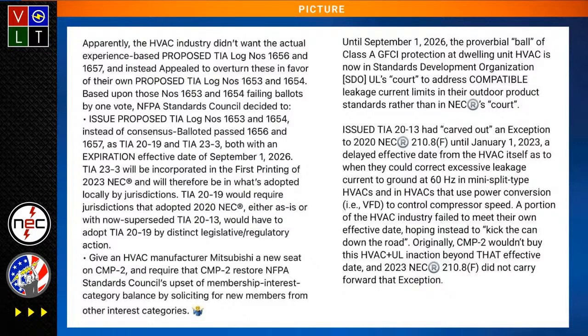There's a lot of these gray areas, and I feel this is kind of the whole point of why we're doing this with Code Making Panel 2, because they're going to focus on this whole GFCI thing. To me, what it seemed like was they were working so hard battling against the HVAC manufacturers when they should have been going out to these boatyards and marinas doing some research on that stuff. They're sitting there measuring leakage current at the AC unit. Dude, no—go out there to these boatyards and marinas.